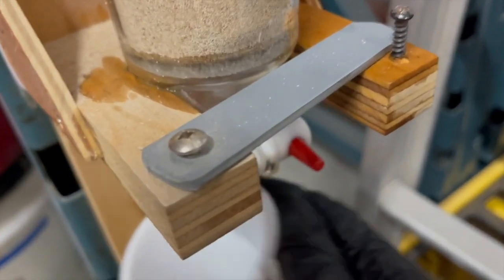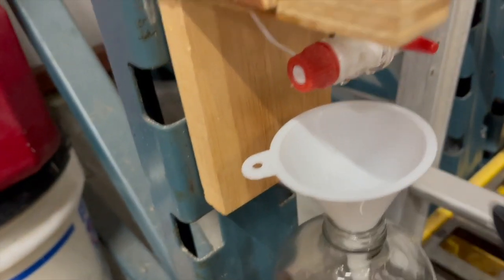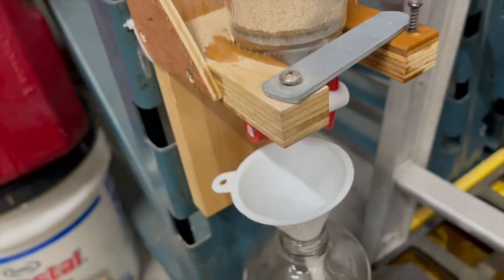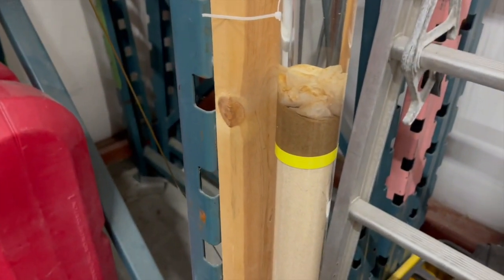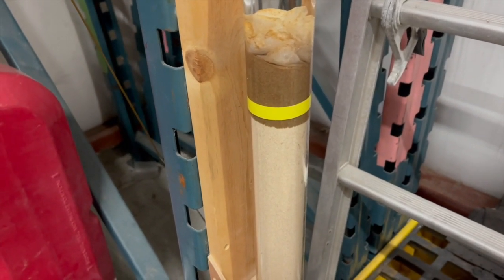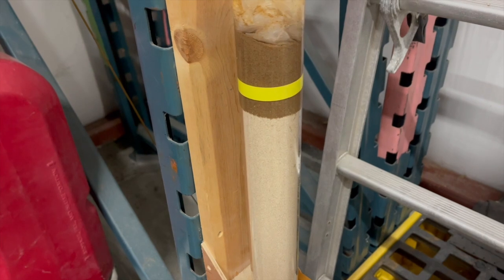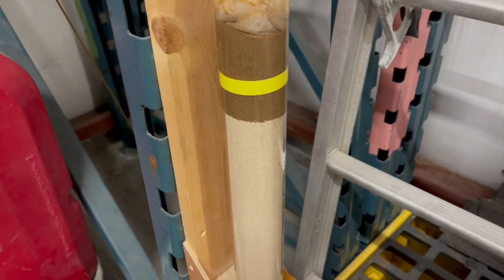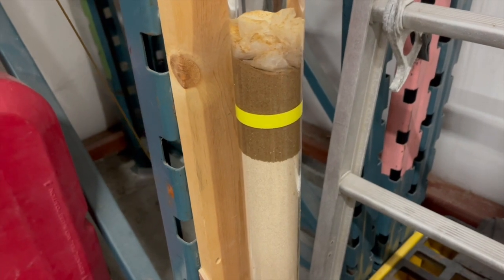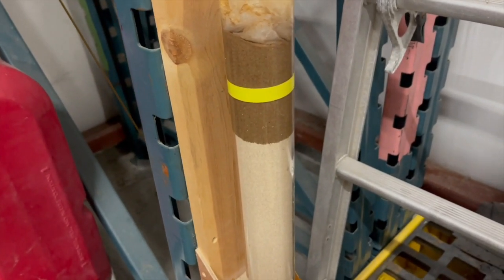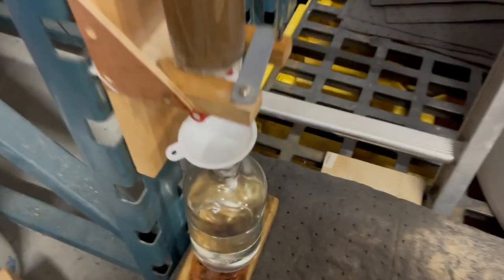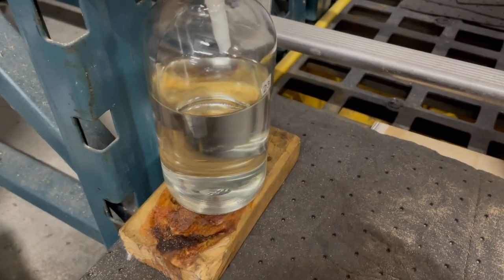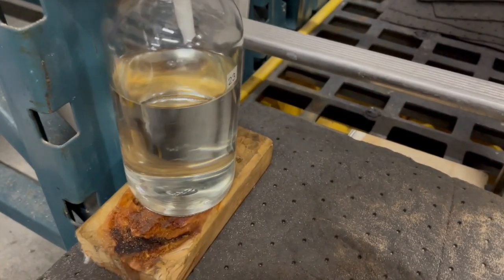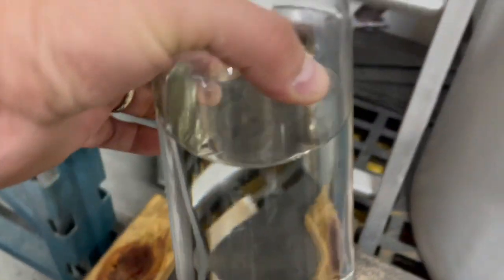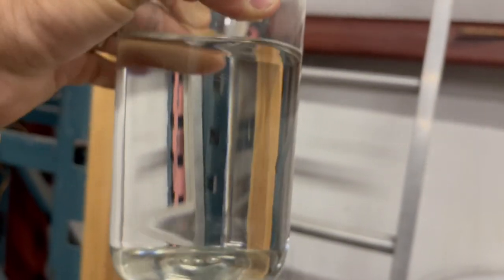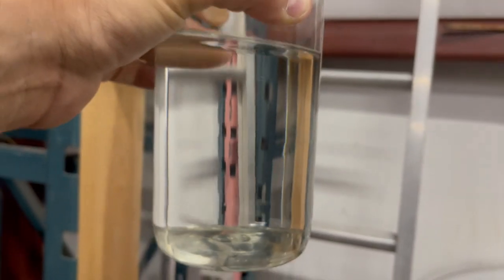And then once I open up the spigot here, you'll see the fuel will start to come out. Now it'll fly down through the clay. And as it goes through the clay, it's filtering out all the stuff that's in the fuel, so it comes out extremely clean, which is why the conductivity is near zero. So after about 15 minutes on our setup, the fuel will filter all the way down into the other sample jar, and you can see here it looks extremely clear. And when it tests out, it should test out to be about 0 to 10 picosiemens per meter, hopefully on the lower end of that scale.